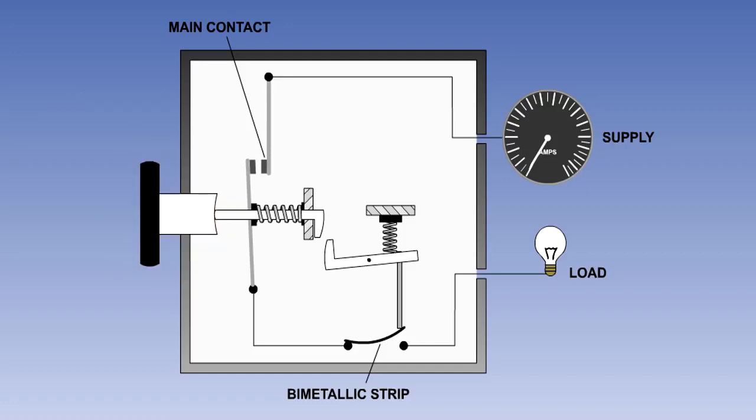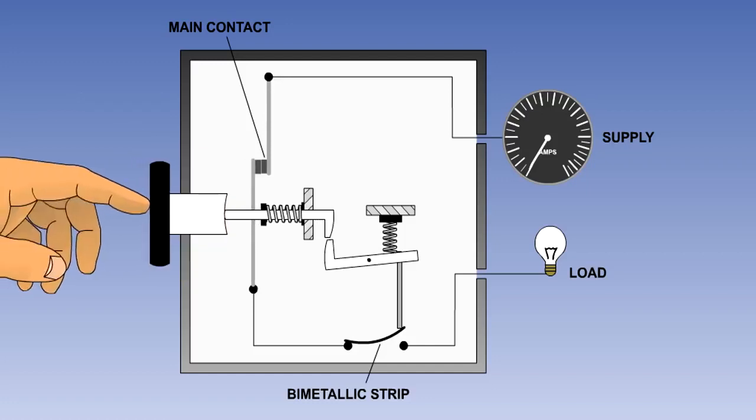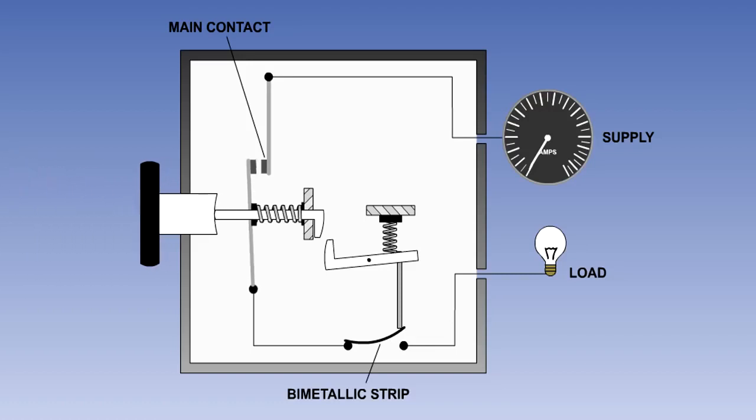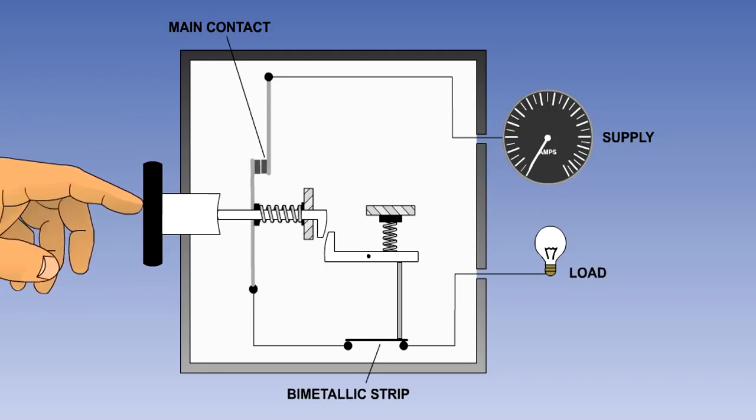If an immediate reset attempt is made, the current will not flow in the circuit, because the bimetallic strip contacts will still be open, and the button will not latch in. Only when the bimetallic strip has cooled sufficiently will the circuit be able to be completed again.